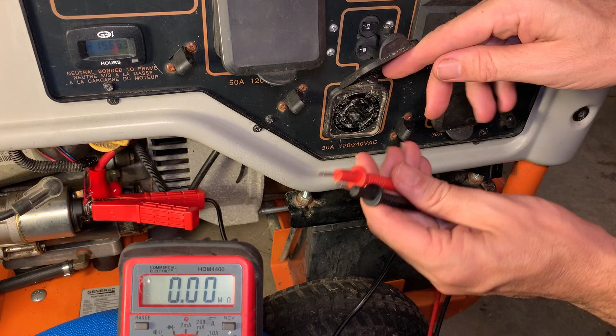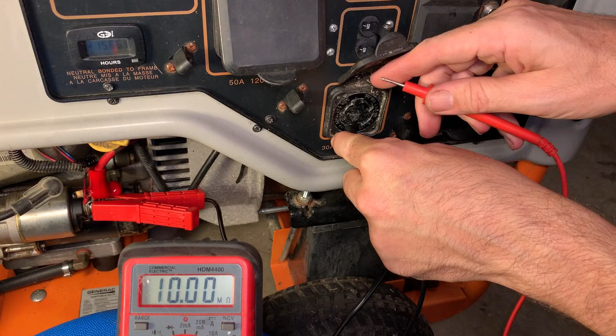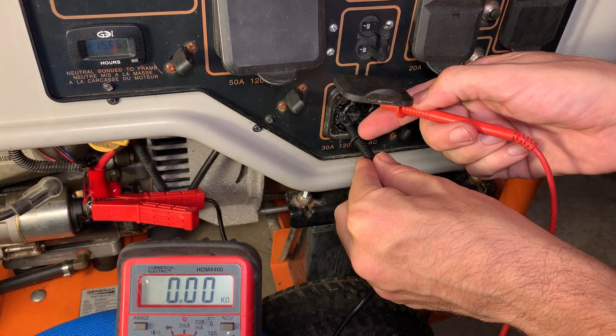So I'm gonna stick one of these probes into the neutral, and then one of the legs. The last one I checked was around 0.3, and that was on a good Generac XG10000e. As you can see, we're at 0.2, so that's a good reading. We'll try the other leg. And pretty much the same. So no red flags here.